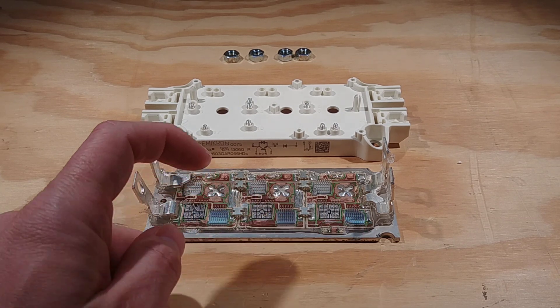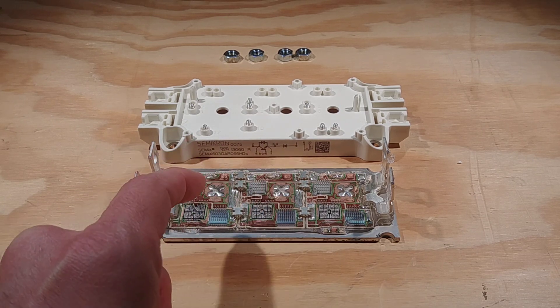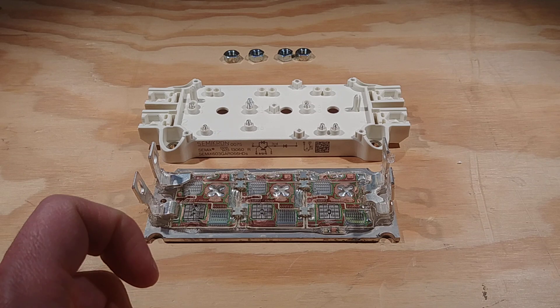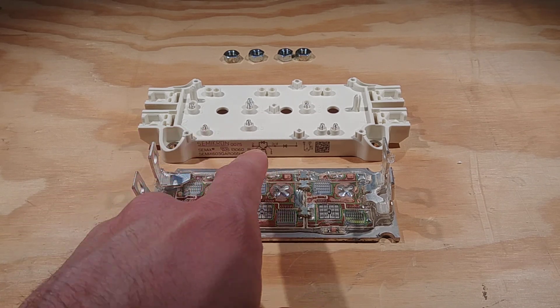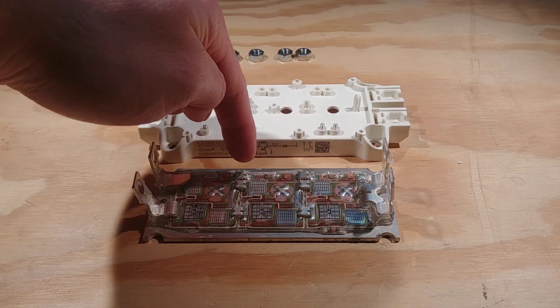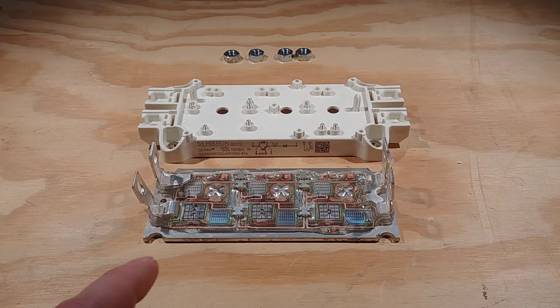That's this section right here. Then on the other side we've got a diode here, a diode here, and a diode here — all in parallel. You can see the links connecting them in parallel. And then we've got some links in the back. The ones in the middle essentially make the mid connection at locations three and four, whereas pin one is the pin that I broke. You can see it actually connects to this bus bar that runs in the back with those two links.